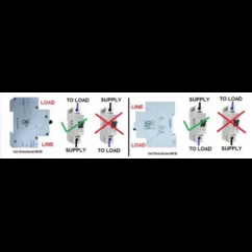When this type of connection diagram or instruction is given on the MCB, you should connect the load at the load point and the supply at the supply point. If you connect it in reverse polarity, there is a chance that your MCB will burn out during overcurrent operation or in a short circuit condition.